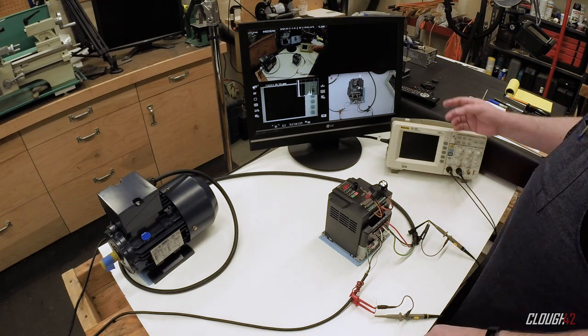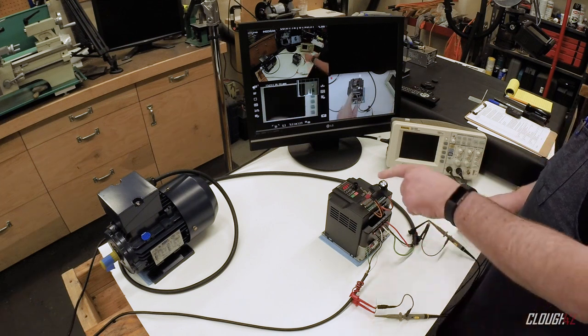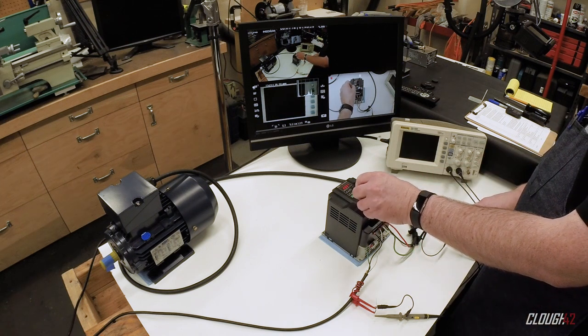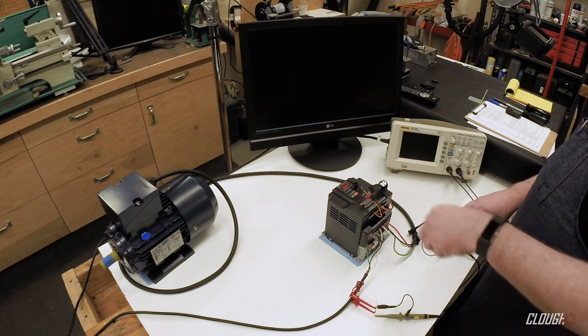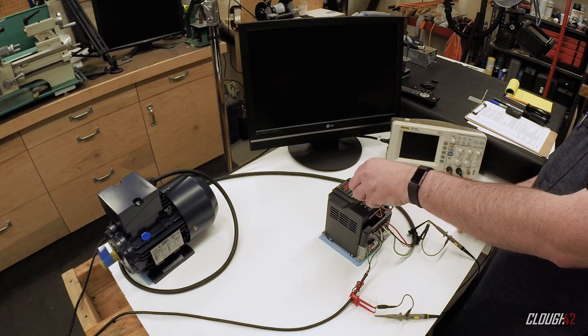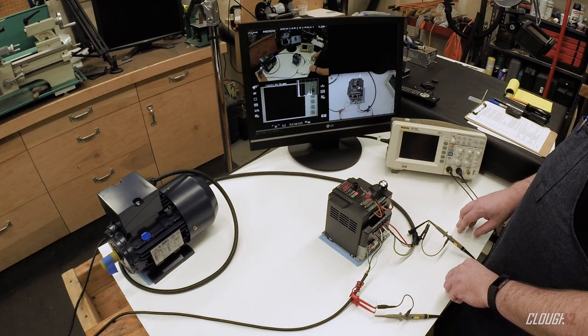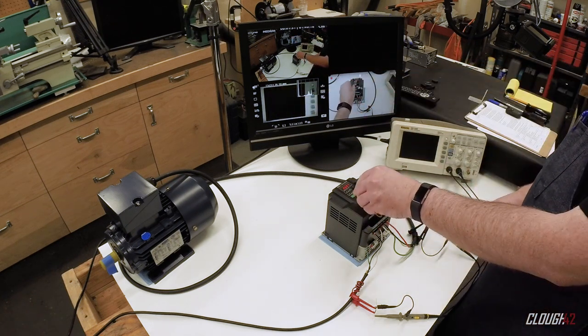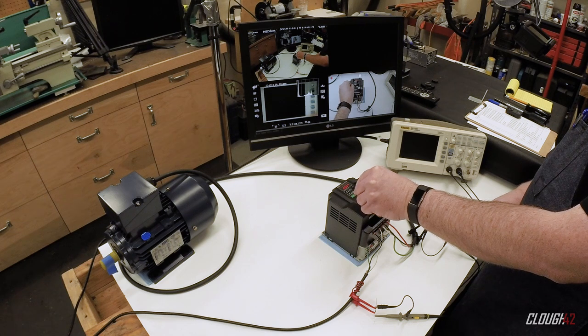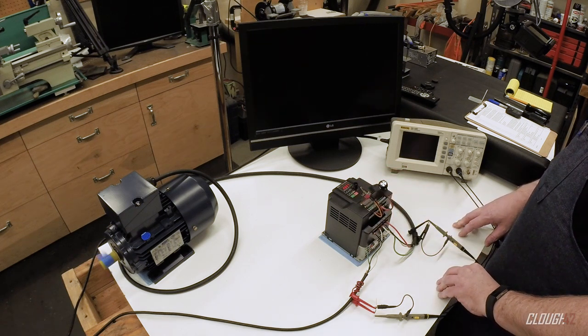Now watch what happens to the monitor when I turn on the VFD. I've just got this set around 20 hertz. You can see the monitor goes completely blank. Now depending exactly where the monitor is in the shop and which circuit it's plugged into, sometimes it just gets jittery and I lose horizontal sync, but sometimes, like right here, it just shuts off completely.